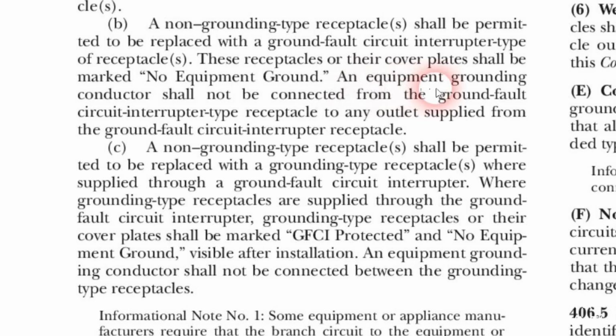(C) A non-grounding type receptacle shall be permitted to be replaced with a grounding type receptacle where supplied through a ground fault circuit interrupter. Where grounding type receptacles are supplied through the ground fault circuit interrupter, grounding type receptacles or their cover plates shall be marked GFCI protected and no equipment ground, visible after installation. An equipment grounding conductor shall not be connected between the grounding type receptacles.